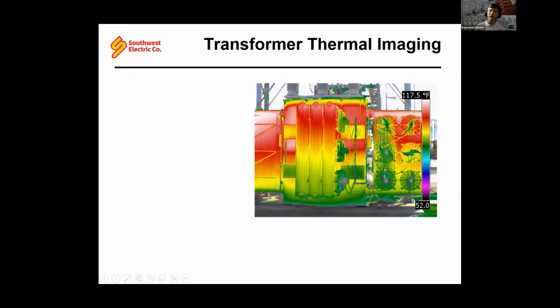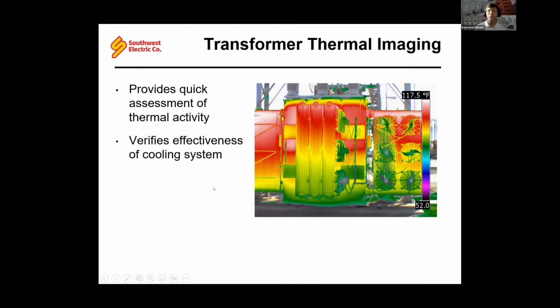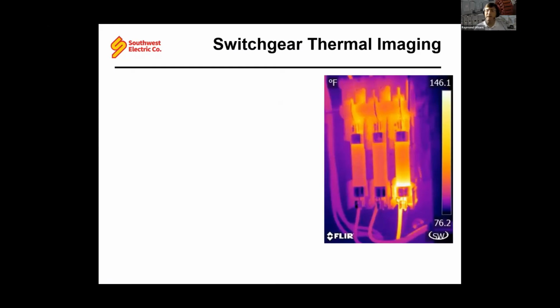If one of these fans was red near the bottom, we would know that it's not operating, and therefore we would know instantly, hey, we need to give some attention to this fan in order to get proper cooling. So this is a fairly simple way, again, as you're there at your transformer doing your sampling, to do a quick IR scan and get more information on how to see if anything unusual is happening.